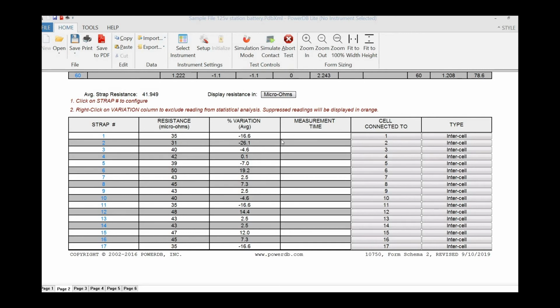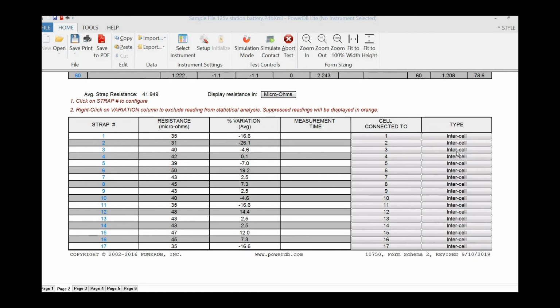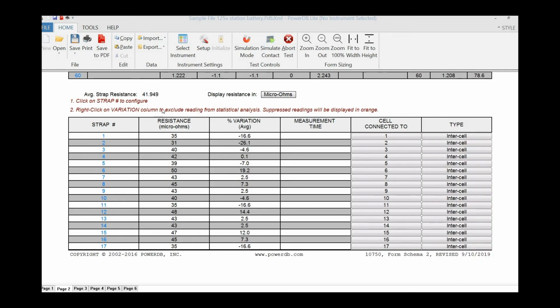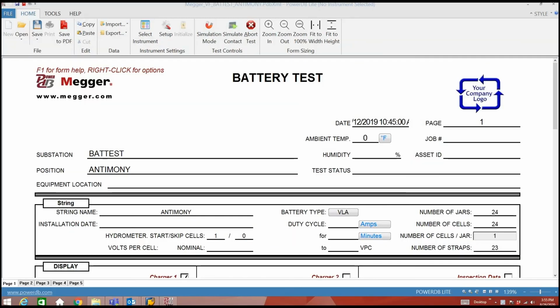You can also select a type of strap, intercell, intertier. There are many choices. Only intercell straps are used as part of the strap average. This is so long straps do not skew the average. You can also right-click on the strap variation value and exclude the strap reading from the average. This ensures that no outlying strap measurements will skew the average.